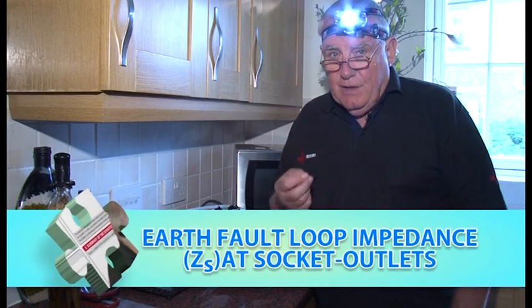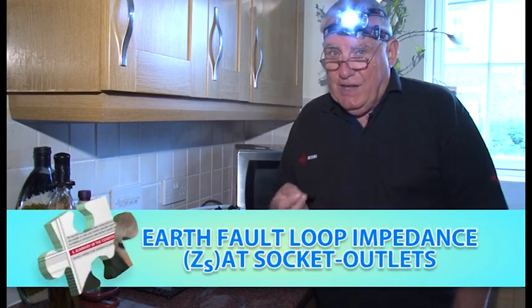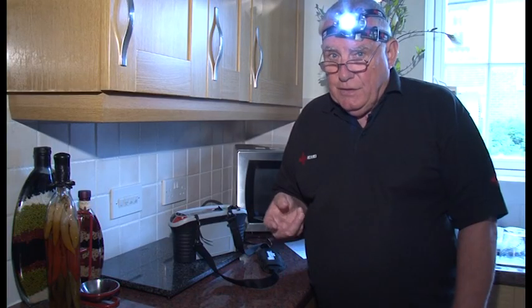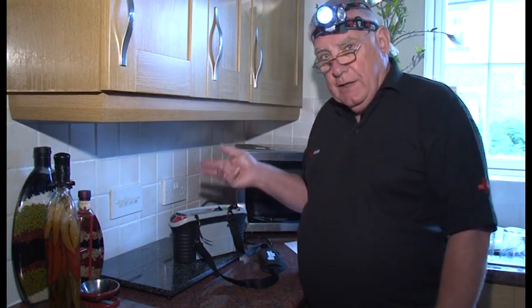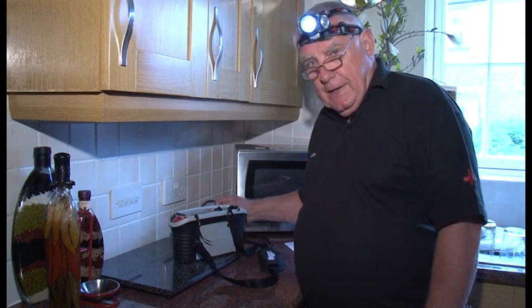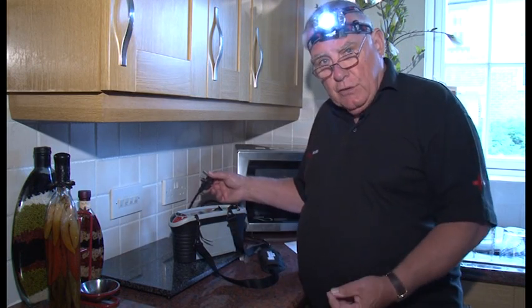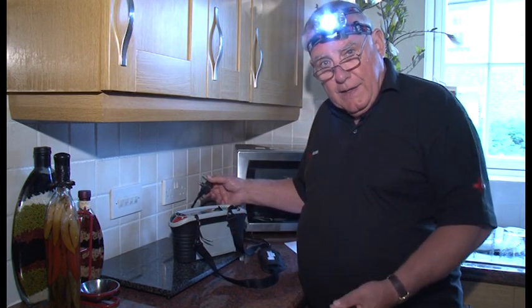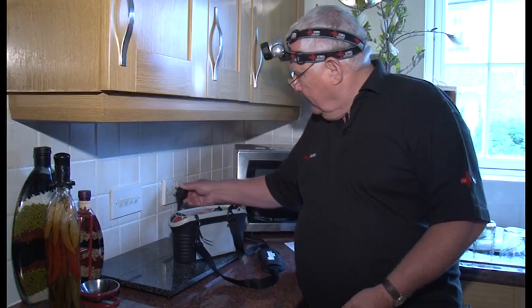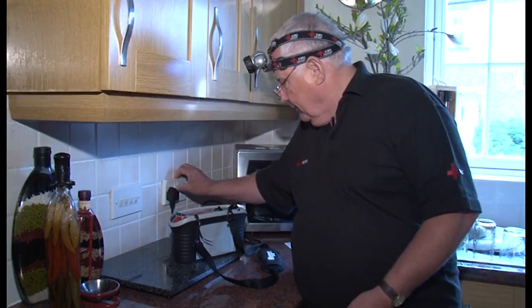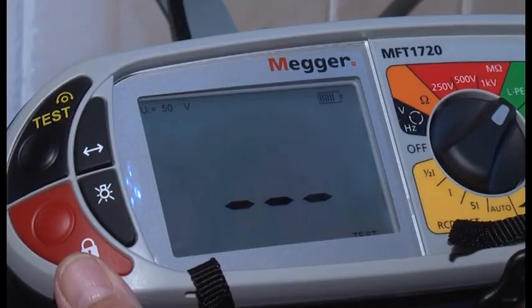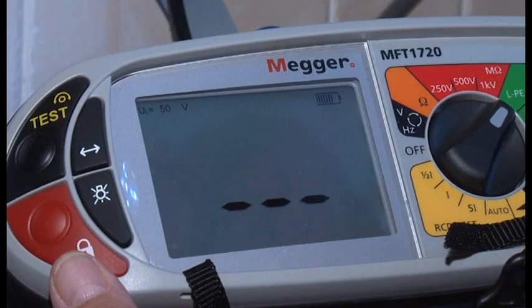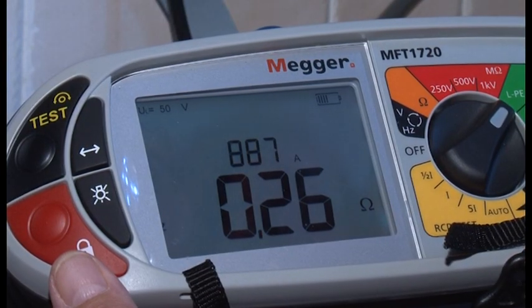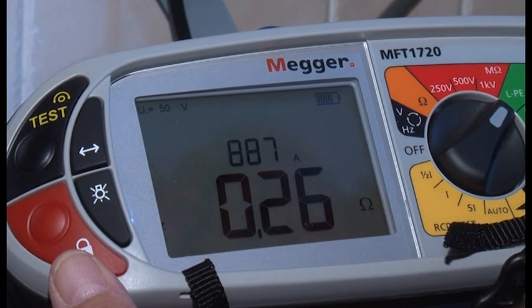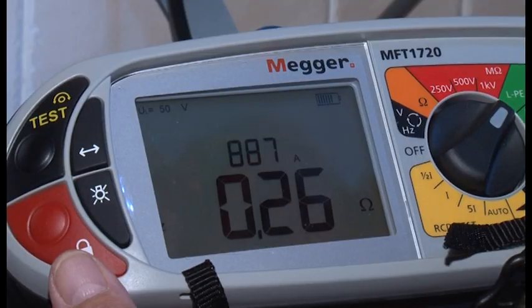To determine the value of ZS for each socket outlet circuit is very easy. All I have to do is to go around to each socket in turn, plug the 3-pin lead in, and whatever the highest reading for that circuit, that will be the reading which I will record. As you can see, I've got a reading for this socket of 0.26 ohms. I will now go and repeat it on all the other sockets.